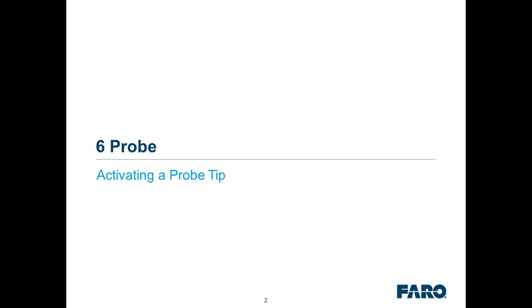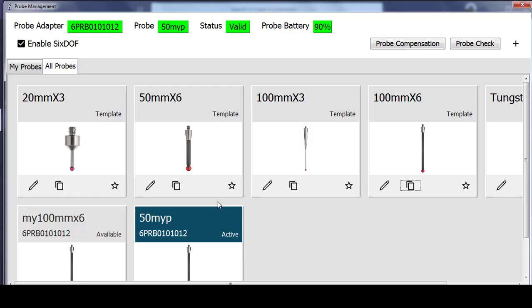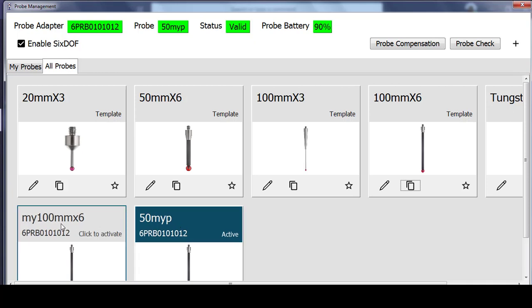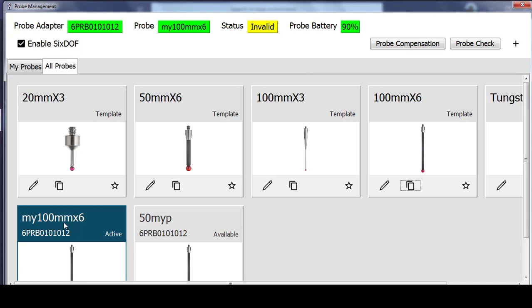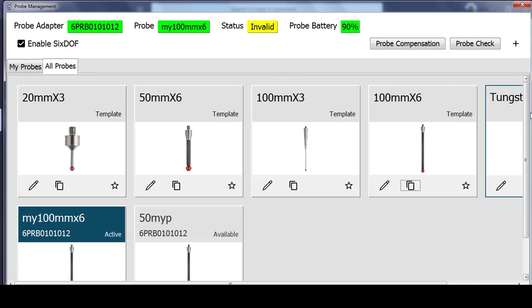Lastly, just to cover one more time how to make a probe active, you select the name of the probe. So if I select the name of my 100 mm probe, it will become active and blue, and you will see the status change to invalid, because I have not previously calibrated that probe.